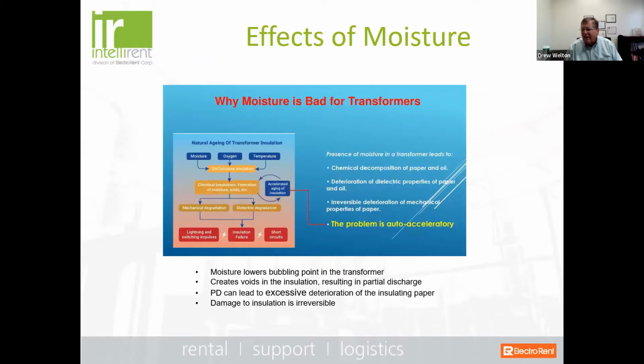Now, why is moisture bad? Well, for a couple of reasons. Number one, and first and foremost, it lowers the bubbling point inside the transformer. And when you do this, this can begin to create voids in the insulation. And this results in partial discharge. That's the first indication that you're starting to get an insulation breakdown.